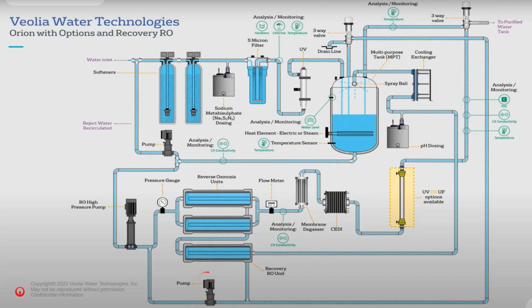This pump here is a concentrate recovery pump, so it recovers the energy from the concentrate, as it has quite a lot of pressure. We can reuse that pressure upstream of the RO here. So with the combination of the RO feed pump and the RO concentrate pump, the electrical load on those two pumps is less than having a single bigger pump on the feed here. Again, we're looking to save energy on that aspect. Once the water passes through the RO unit here, we have another conductivity cell, just to make sure that the RO is operating correctly. And then there's an option for a degassing membrane. The degassing membrane is here to remove any CO2 that may come through, as this adds an additional load onto the CEDI. So it depends on your raw water analysis whether we need the degasser or not.